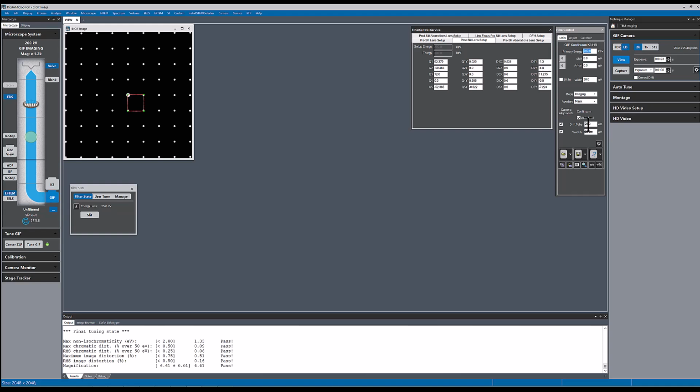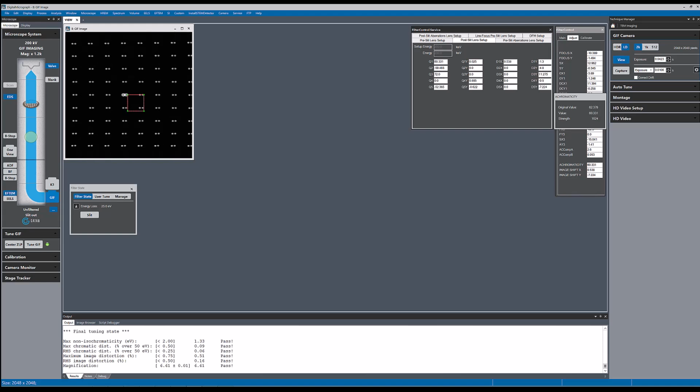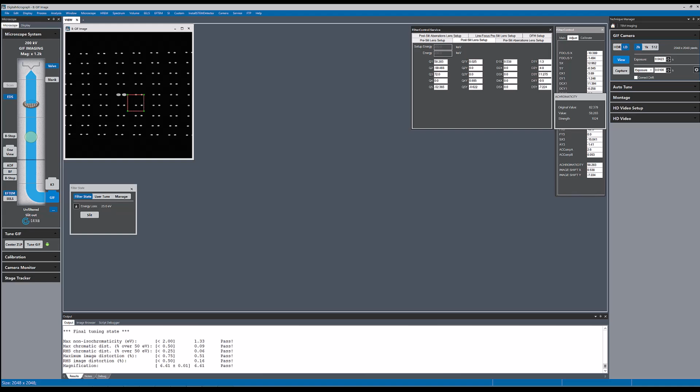At the moment the chromatic blurring is very minimal because the chromaticity is well corrected. So what we're actually looking at is two images that are 25 eV separated in energy loss, but with no aberration. I'm going to introduce some chromaticity and show you the effect. If the chromaticity is bad, you can see that's the effect. You can imagine how that would look in an image: you'd have your features smeared out over the camera. It's very clear here because we have this mask pattern.